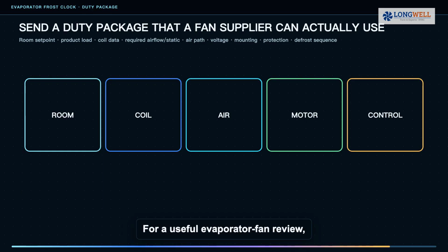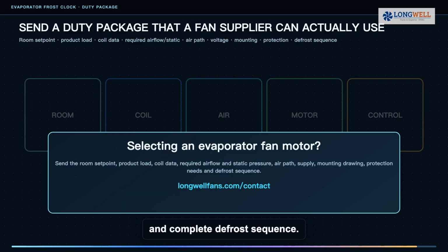For a useful evaporator fan review, send the room set point, product load, coil data, required airflow and static pressure, supply and return path, voltage and frequency, mounting drawing, protection requirements and complete defrost sequence. Longwell can then review a real duty instead of guessing from fan diameter.